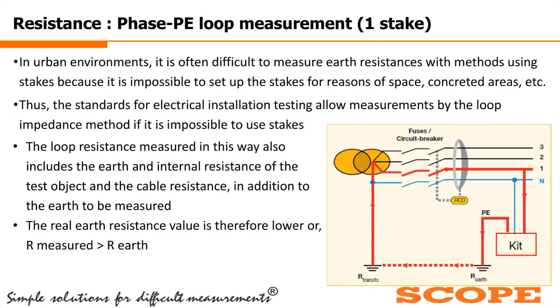Then the next one is the phase to PE loop measurement method using a single stake. In urban environments, we cannot insert these earthing spikes, or whatever the earth rods, at the time of measurement if there are any limitations of space or concreted areas. So in this type of practical problem, we can also use this single stake method, using the phase to PE loop measurement method.